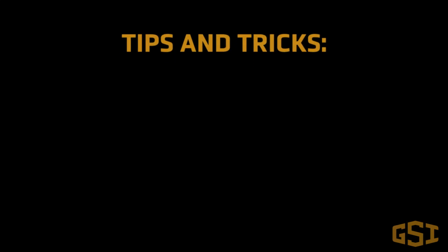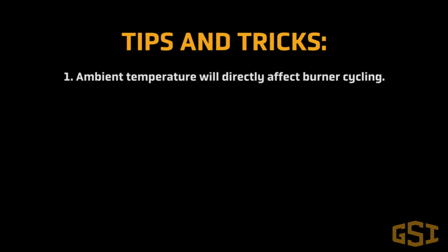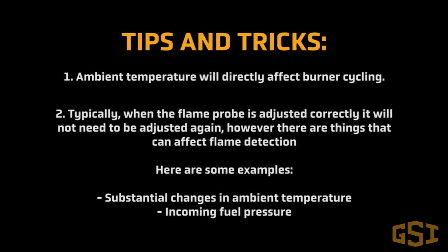Tips and tricks. Ambient temperature will directly affect burner cycling. For more information on burner cycling, look for GSI videos on burner cycling. Typically, when the flame probe is adjusted correctly, it will not need to be adjusted again. However, there are things that can affect flame detection. Here are a few examples: substantial changes in ambient temperature, incoming fuel pressure.